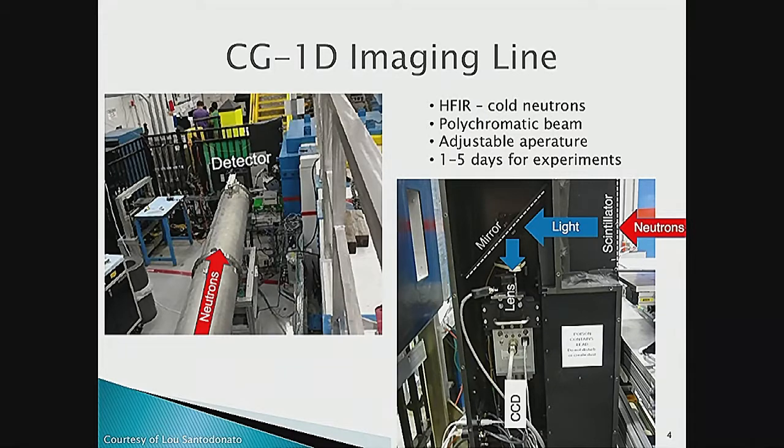But as Ben's going to talk about, we are going to do a new sample setup at the line, and so we need to see what the open beam is like and what the radiation is like. So we were able to see the safety precautions that take place when they have a new type of experiment going on. And unfortunately, with our open beam, we did get 5 millirem outside of that fence line, so we had to push back that caution area with ropes.